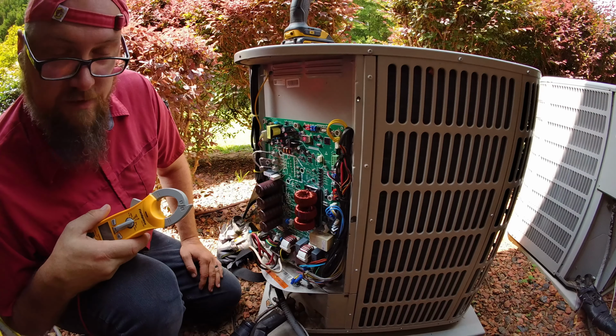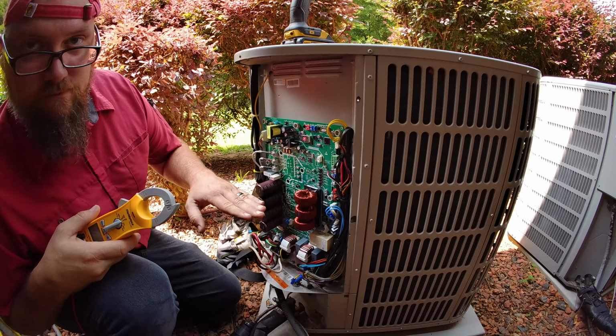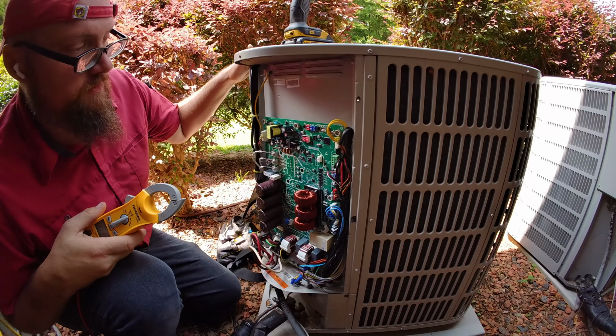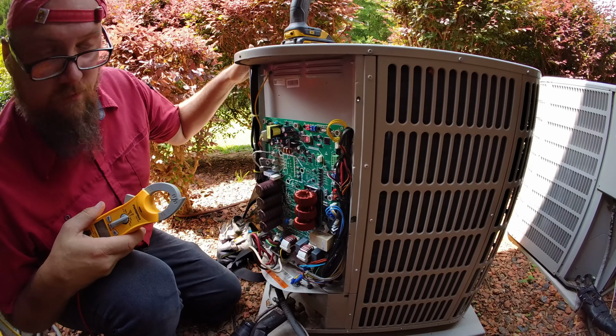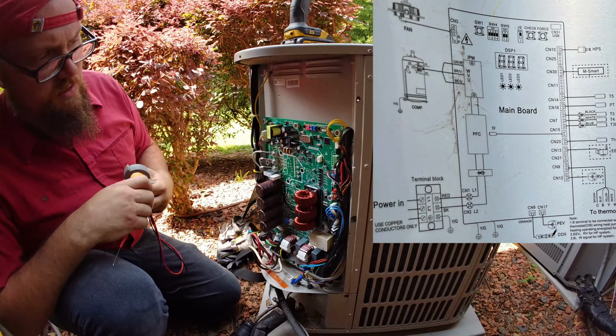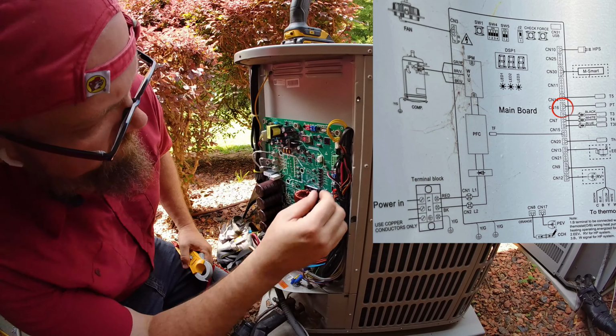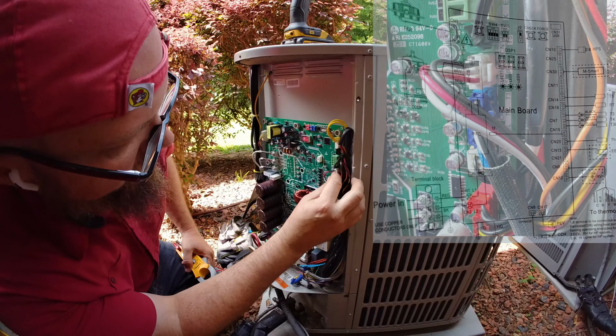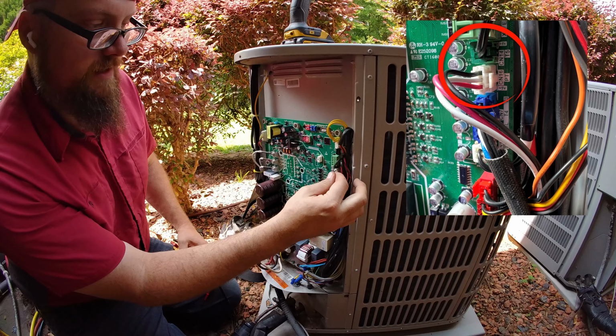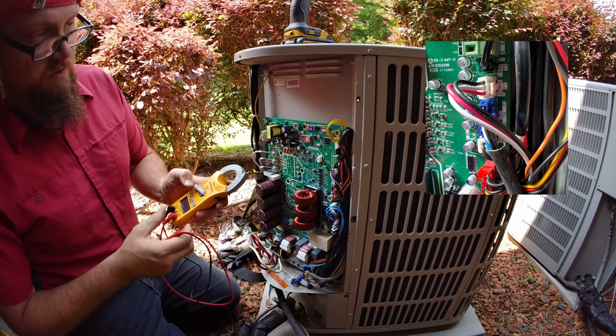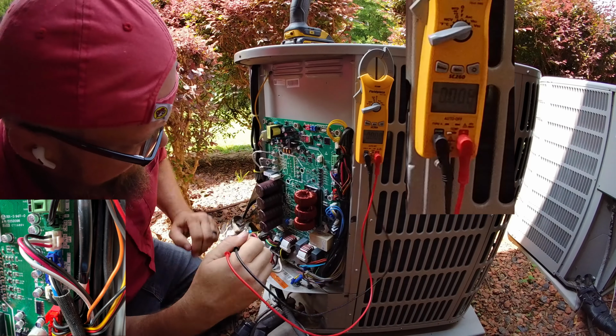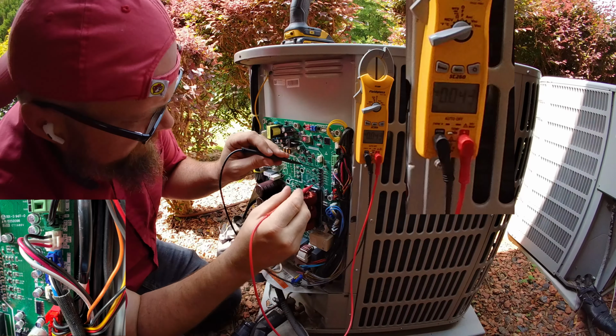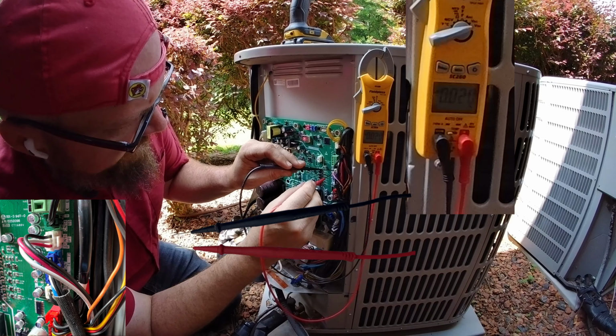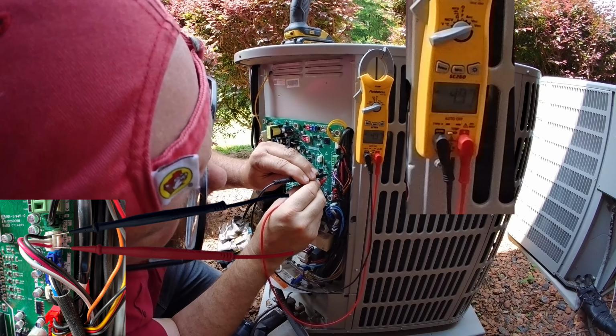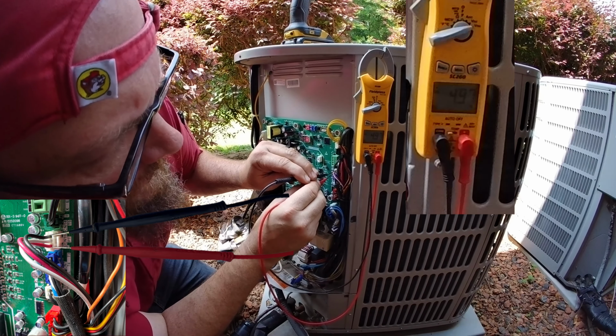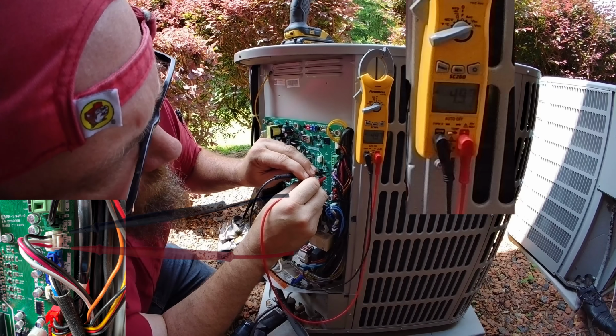And as it's doing all that, it's using that information to decide how to modulate the compressor and fan motor on this guy to better accommodate whatever particular load is going on. So to check the transducer here, I believe we're looking for C16, which is this little red, black, and white plug-in here. So we want to go over to DC mode, and if we look between, I believe it's red and black, if I remember, we should see somewhere between 4.5 and 5 volts DC, and we're seeing 4.9.